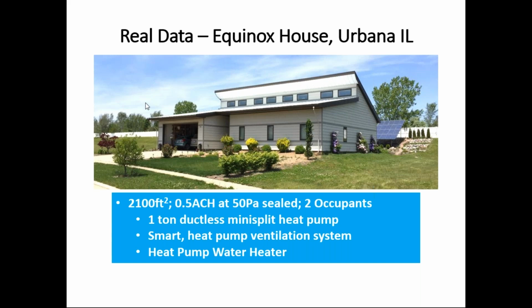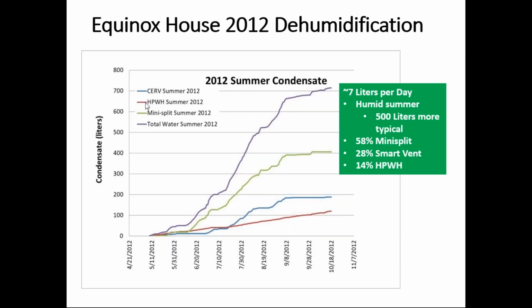So this has a 1-ton ductless minisplit heat pump, a smart heat pump ventilation system, and a heat pump water heater. And here's some data. In the report that we posted in October on these dehumidification systems, there are 4 summers of data. So you can see between a humid summer and a dry summer, this is our typical summer, but fairly humid. Over the course of the summer, we pull out about 700 liters of water going from May up through September. And you can see how the moisture is divvied out.